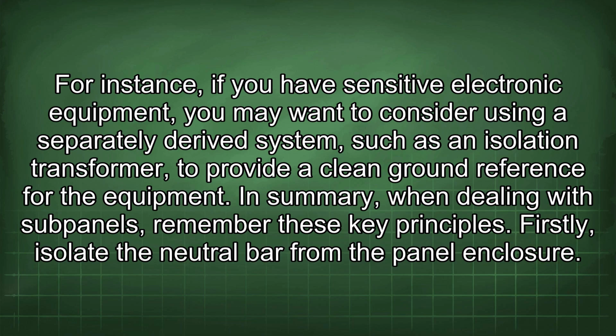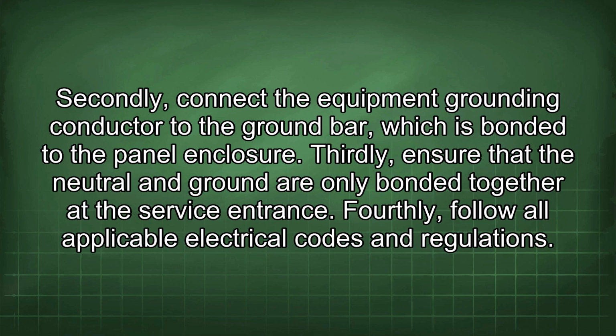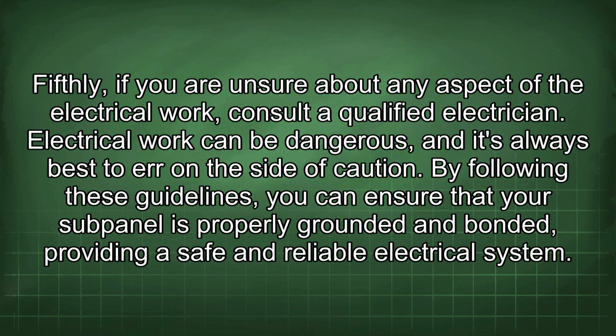In summary, when dealing with subpanels, remember these key principles. Firstly, isolate the neutral bar from the panel enclosure. Secondly, connect the equipment grounding conductor to the ground bar, which is bonded to the panel enclosure. Thirdly, ensure that the neutral and ground are only bonded together at the service entrance. Fourthly, follow all applicable electrical codes and regulations. Fifthly, if you are unsure about any aspect of the electrical work, consult a qualified electrician.